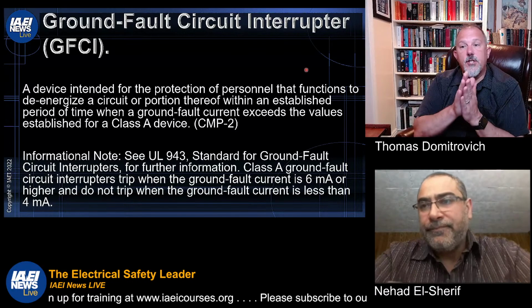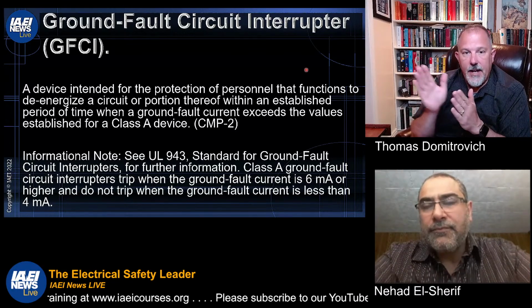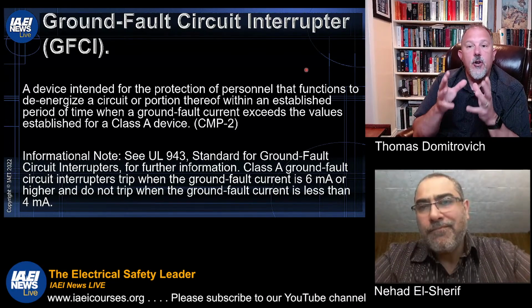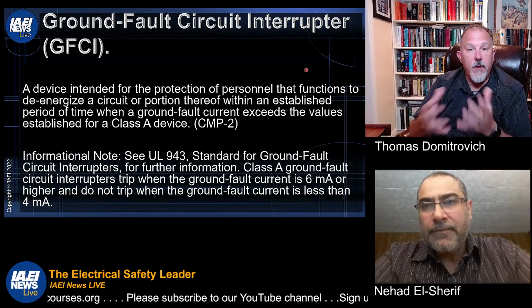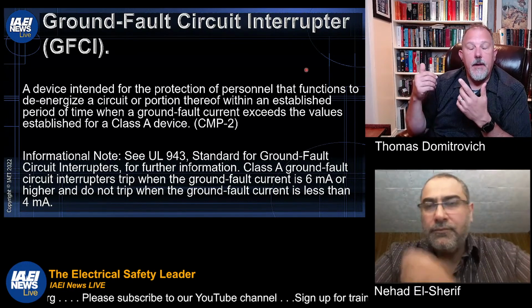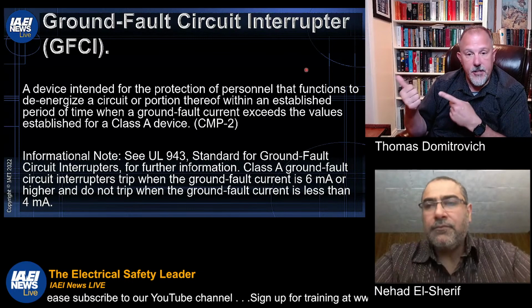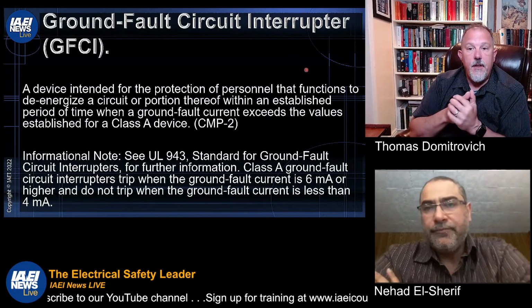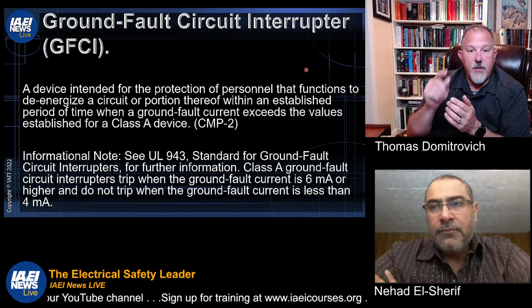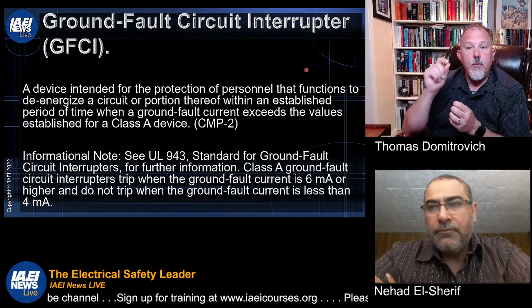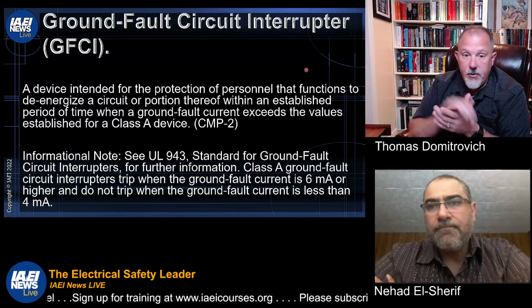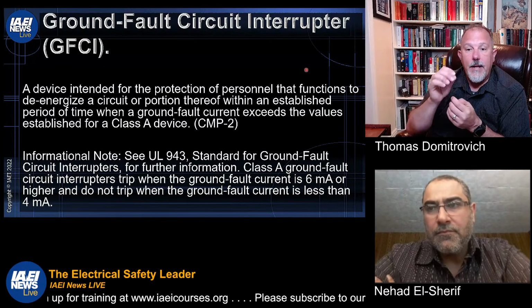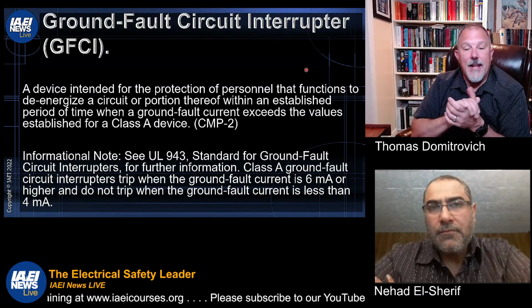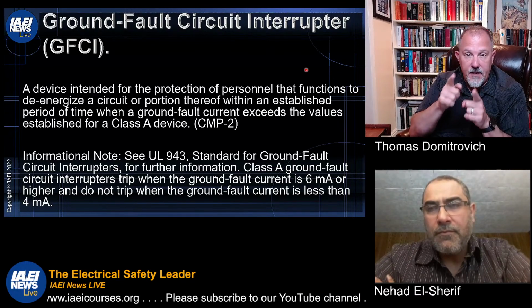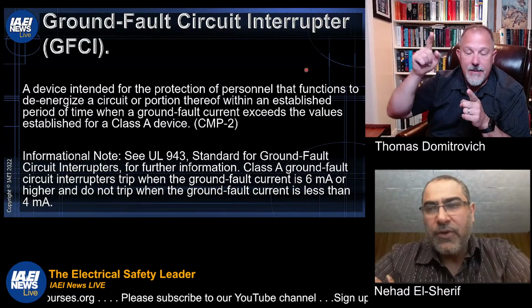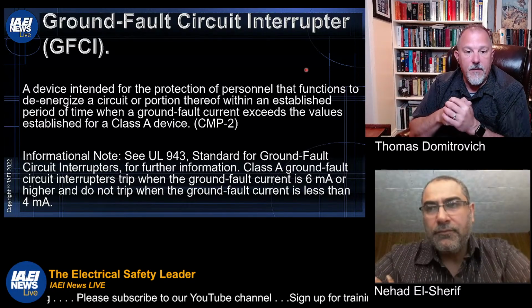Yep. And if you look at this definition, anytime you see the words ground fault circuit interrupter, it falls back on this definition, which tells you that it functions to de-energize that circuit within an established period of time, which is what you just spoke to, when the current exceeds the values established for a Class A device. We're going to understand the difference between Class A, C, D, and E, and we'll throw B in there for discussion as well.